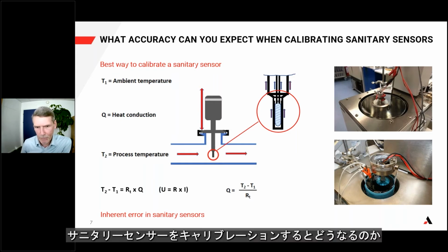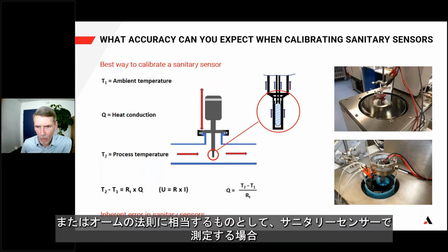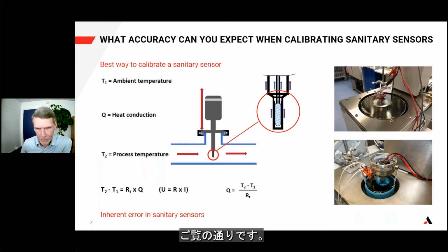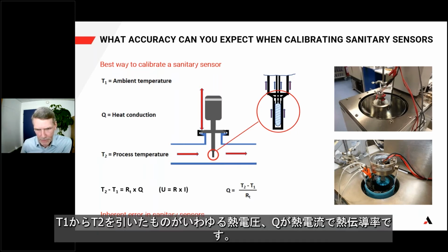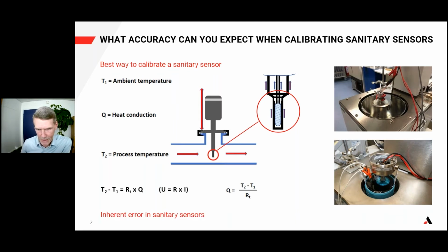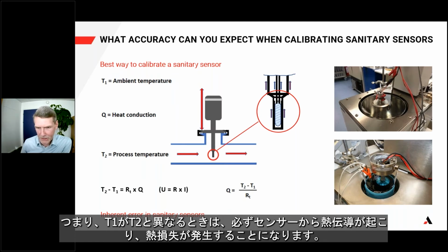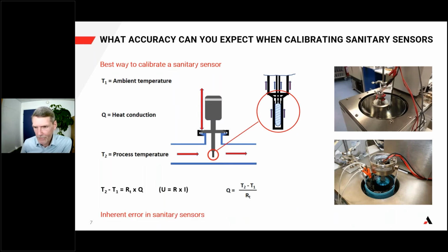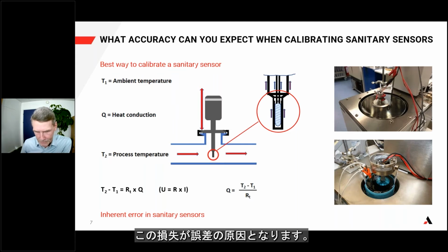What happens when calibrating a sanitary sensor or measuring with a sanitary sensor? As an equivalent to Ohm's law, we have the thermal law. As you can see, T1 minus T2 is, so to speak, the thermal voltage, and Q is the thermal current, the heat conduction. That means whenever T1 is different from T2, we will have a heat conduction out of the sensor, a heat loss. This loss will cause an error.